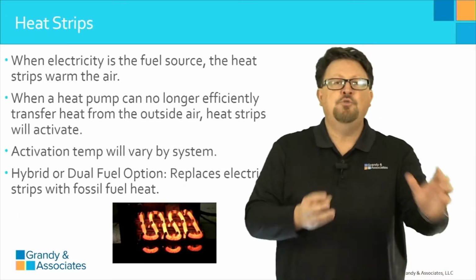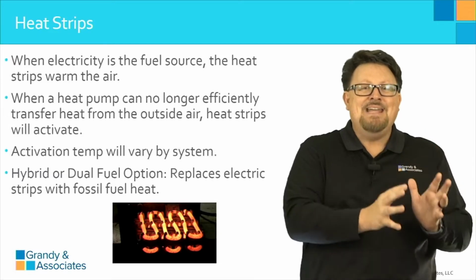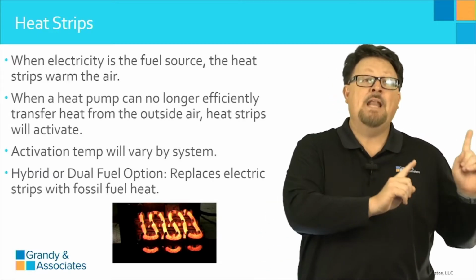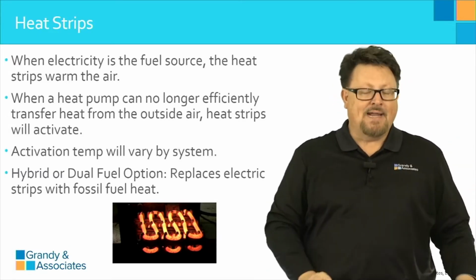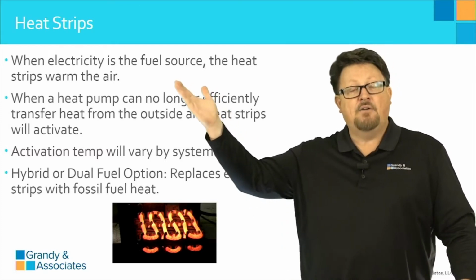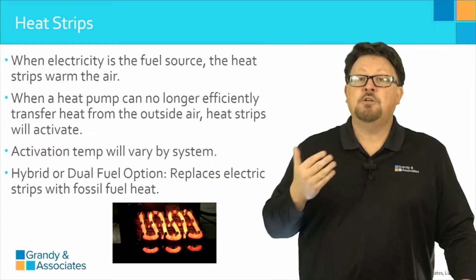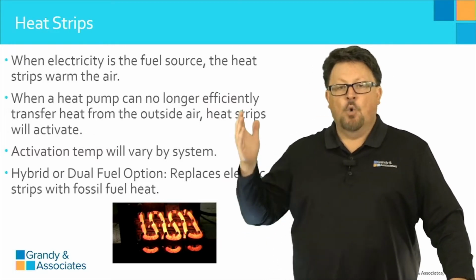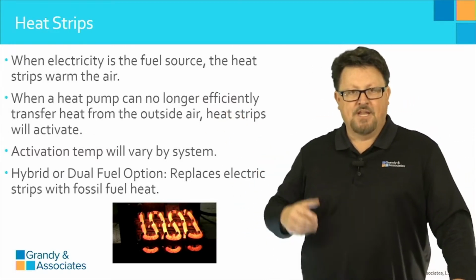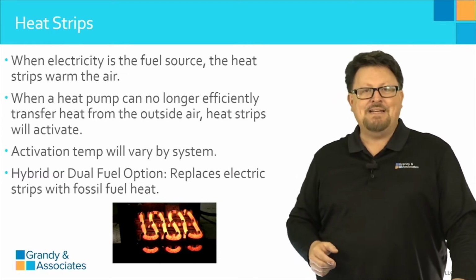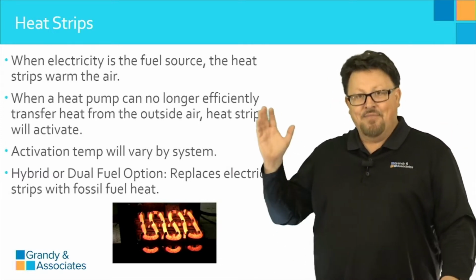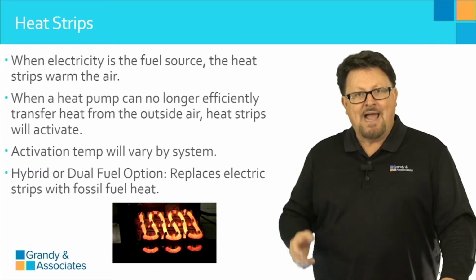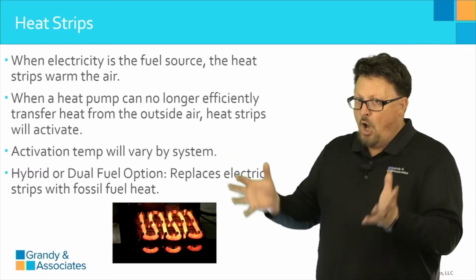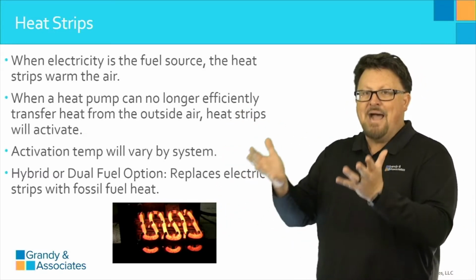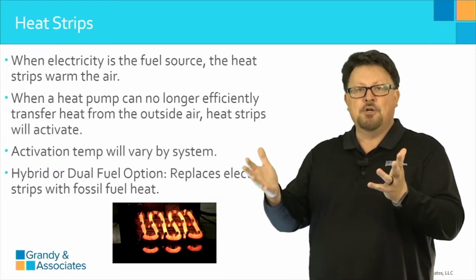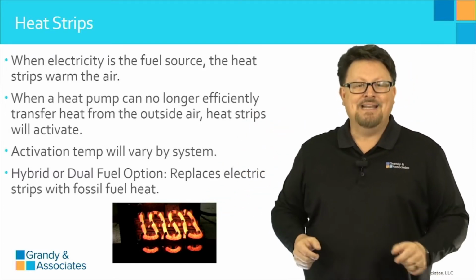Now, here are a few distinctions of the heat pump package unit that we did not see in the gas package application. We have heat strips or auxiliary heaters. When the heat pump package unit can no longer efficiently transfer heat from the outside air, these heat strips will activate. We don't want these running all the time.